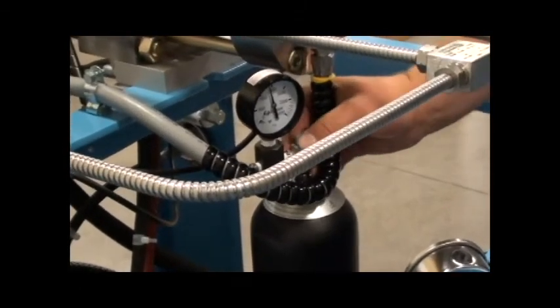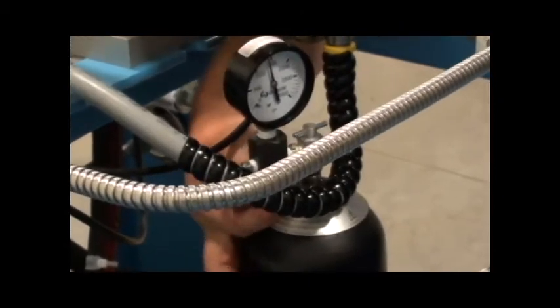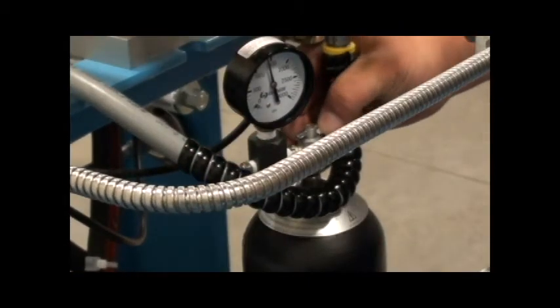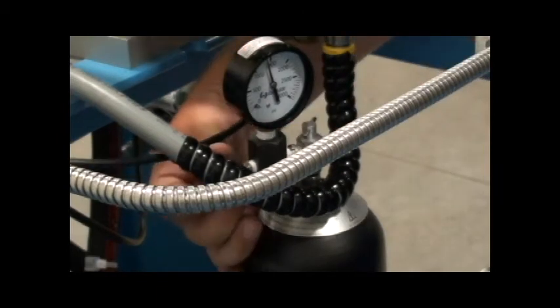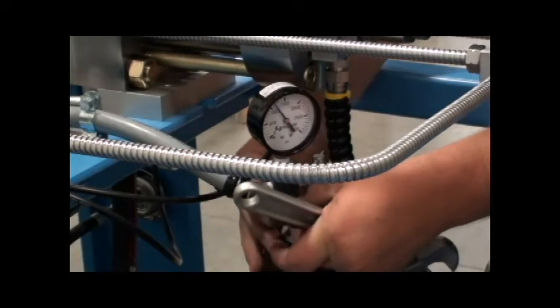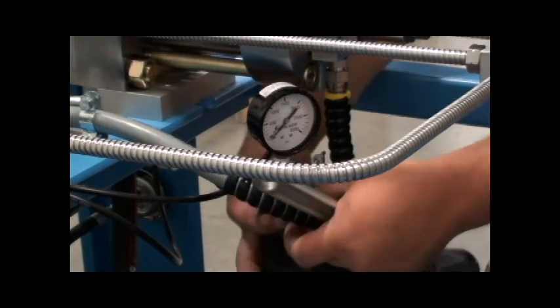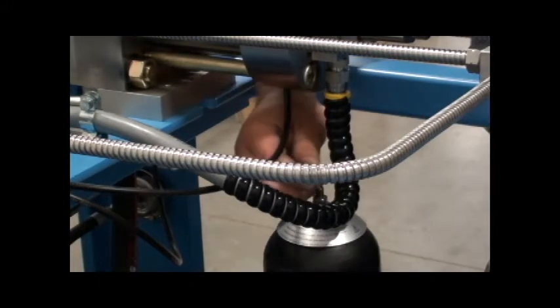Turn the needle valve on the gauge assembly slowly clockwise and observe the pressure reading. The pressure should read 1,500 to 1,800 PSI. If the pressure is sufficient, turn the needle valve fully clockwise to close it, then turn the bleed valve slowly counter-clockwise to relieve any pressure. Disconnect the gauge and hose assembly and reinstall the caps.